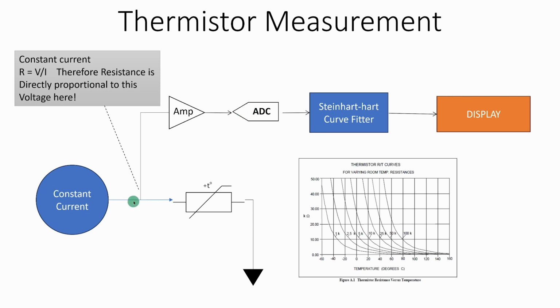So all we have really is a constant current source going through a resistor. We then branch off with a high impedance input to an amplifier. High impedance because we don't want any current to go through there. That gets passed to an analog to digital converter, and then in our microprocessor we do something called the Steinhart-Hart equation. Steinhart-Hart is a way to approximate these curves, but what we want to do is solve an equation to enable us to pick a resistance and turn that into a temperature. Having done that, we can then of course just display and process the temperature as we need to.